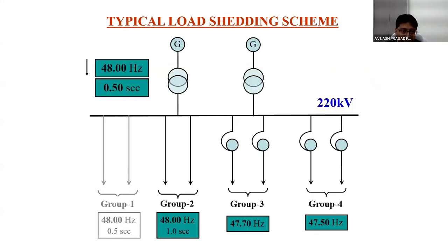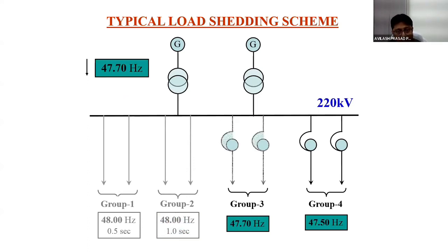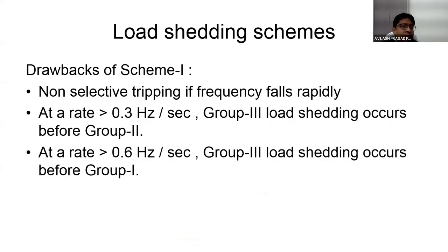Similarly, if the frequency further reduces for more time, that is for 1 second, then the loads connected in group 2 get shed. If the frequency further falls to 47.7, then the loads of group 3 get disconnected. Similarly for group 4, at 47.5 Hz, group 4 will be shed. The drawback of the load shedding scheme is non-selective tripping if frequency falls rapidly. At a rate greater than 0.3 Hz per second, group 3 load shedding occurs before group 2. And if it is at a rate of 0.6 Hz per second, then group 3 load shedding occurs before group 1.